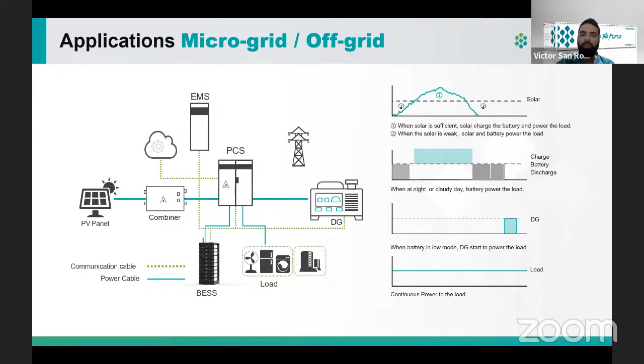The backup scenario is pretty easy. As I told you before, you can charge your battery bank from the grid or from solar panels if you have them. But if you just want a backup system, you don't discharge the batteries at any time, only when there's a failure from the grid. The batteries stay charged all the time, and only when the PCS, through some meters, sees the grid go to low voltage or go completely out, will the battery discharge so you can still use your loads. We can also include backup in other systems, but if backup is your main focus, you charge batteries from solar, wind, or grid, and discharge when there's a failure for the loads. This is another application we have.